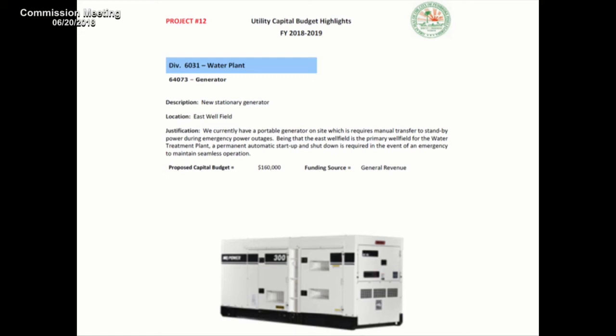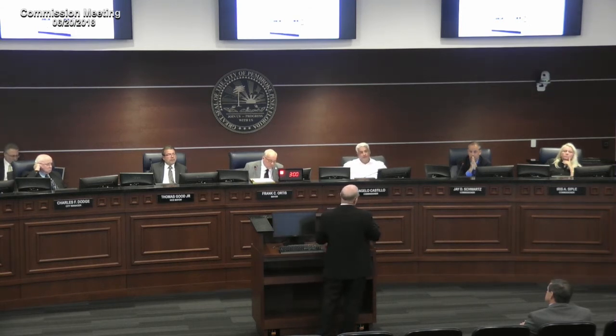Question, Mr. Schwartz? What technology is in place for someone to monitor the 3 well fields during a storm and see whether or not they're online or offline? Very good question. The plant has the SCADA system where computers are hooked up to every pump, each with a sensor. The sensor reads the line pressure, and when pressurized, it talks to the computer and tells the operator what the pressure is. So if the power goes out, the pressure goes to 0, and he's alerted.